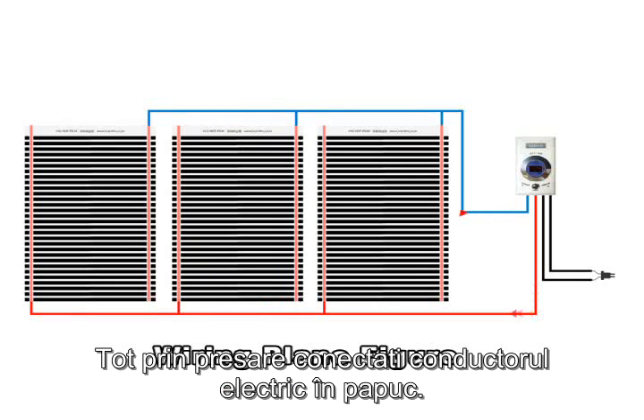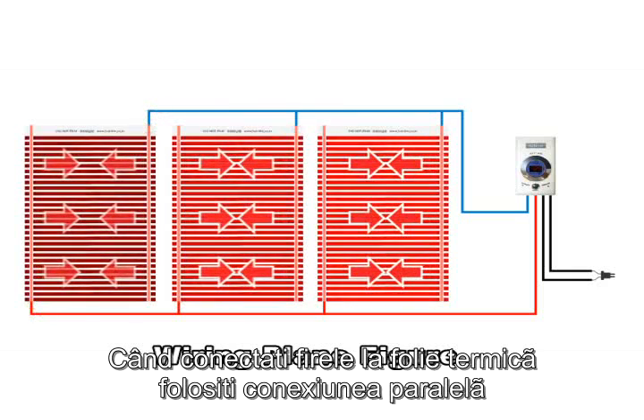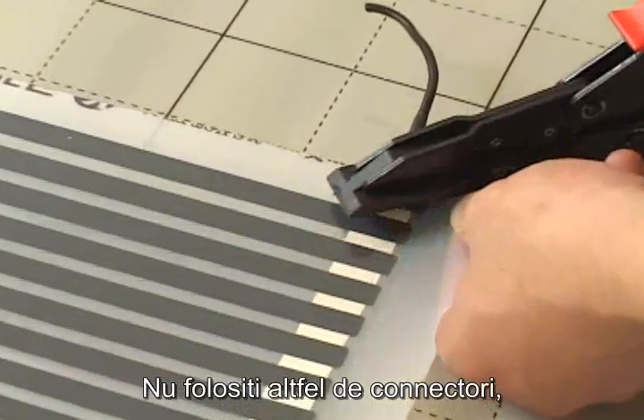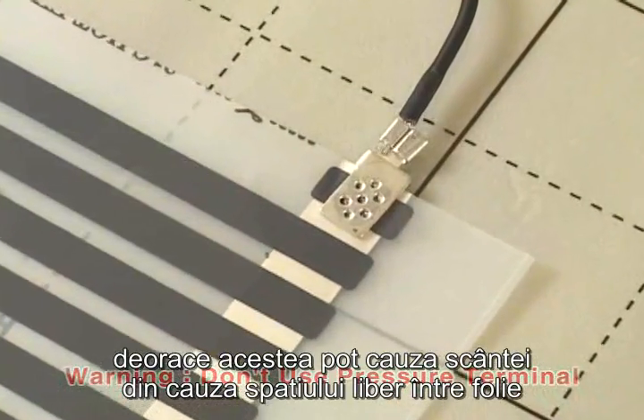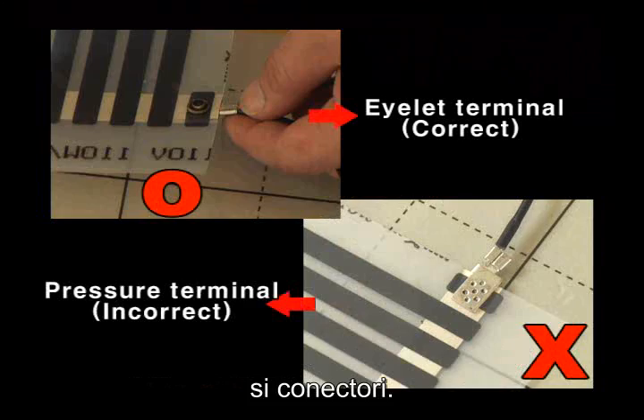With pressure, pliers connect the terminal with the wire. When connecting a wire to a hot film, use parallel connections or diagonal connections for maximum heating effect. For heating film, the pressure terminal is seldom used for connection terminal, because the pressure terminal may cause sparks due to the loose space between the film and the pressure terminal.